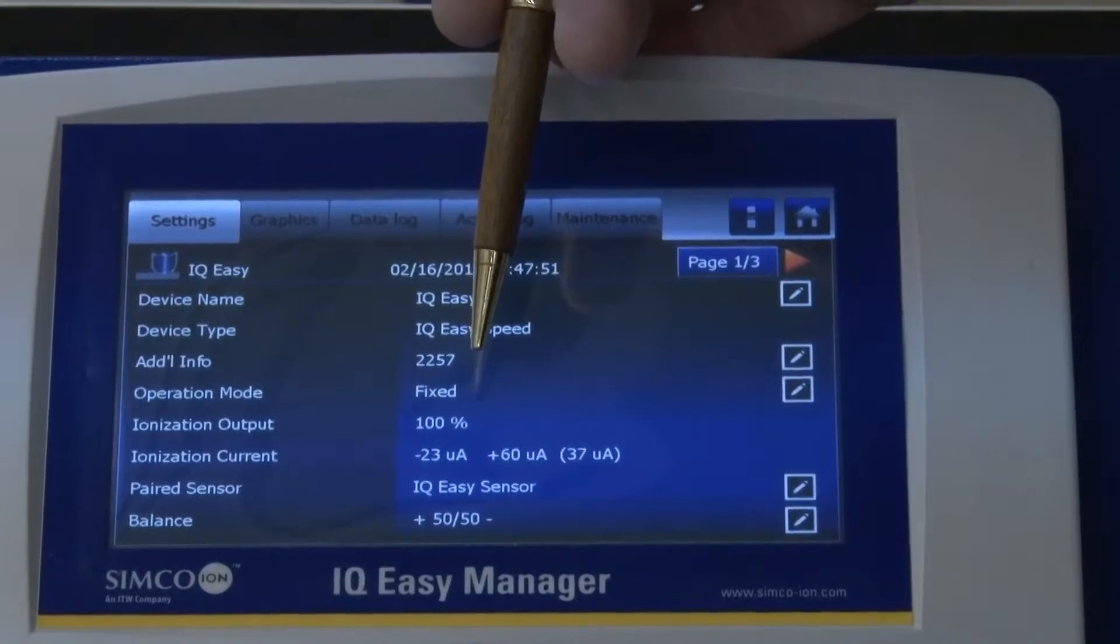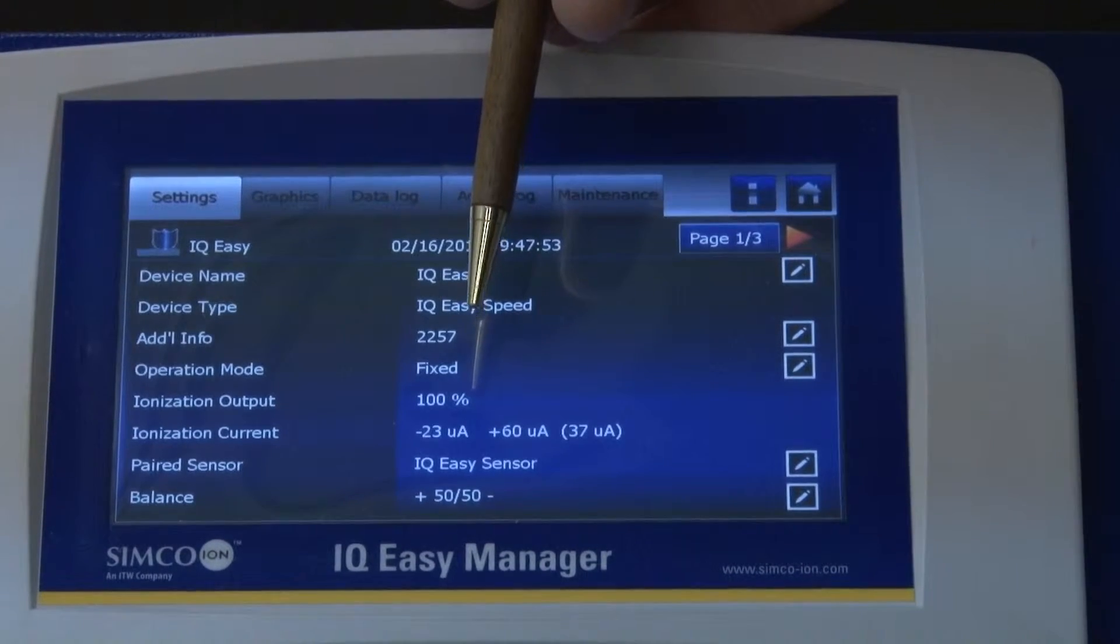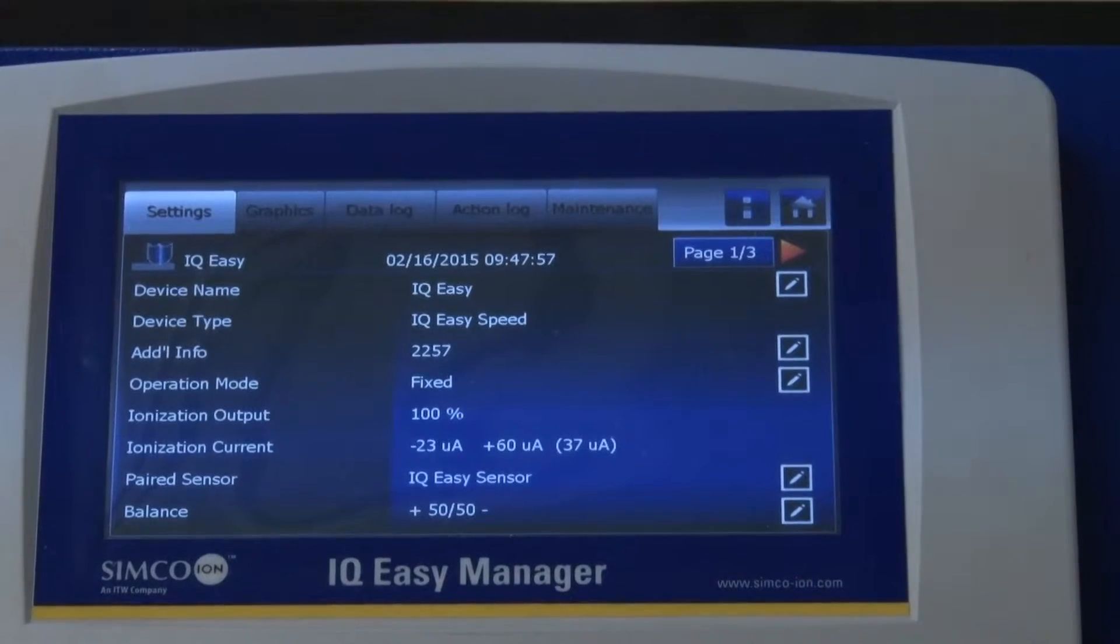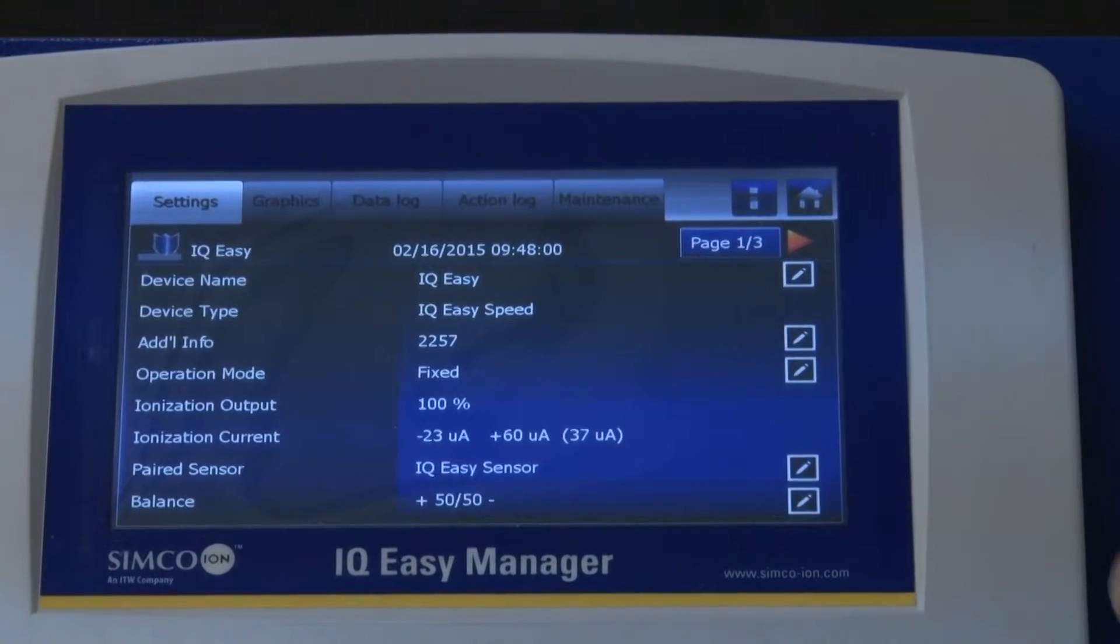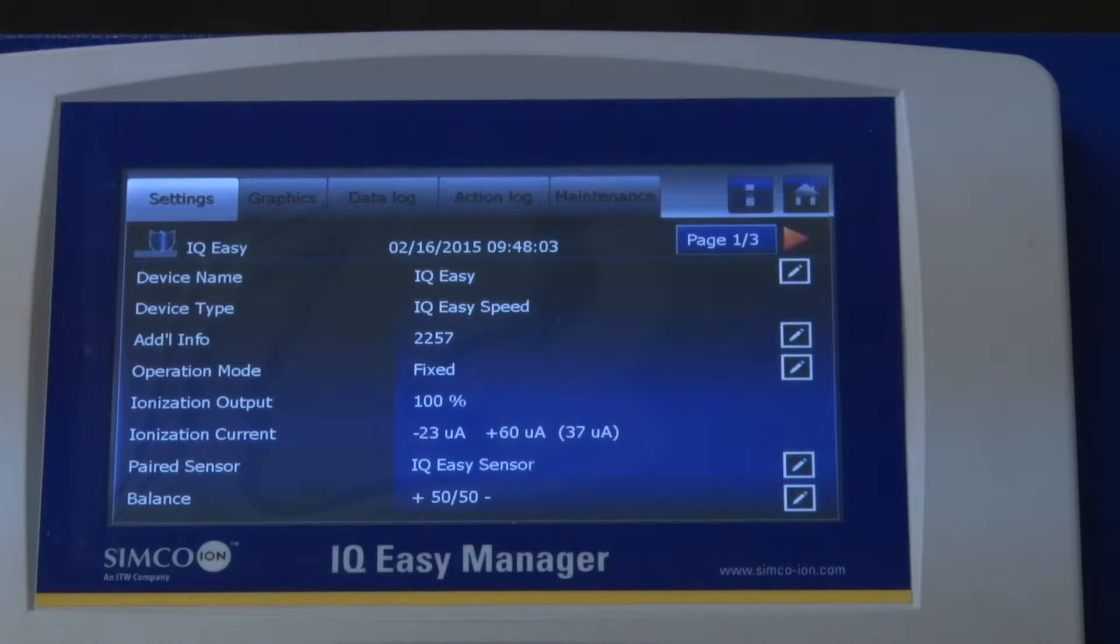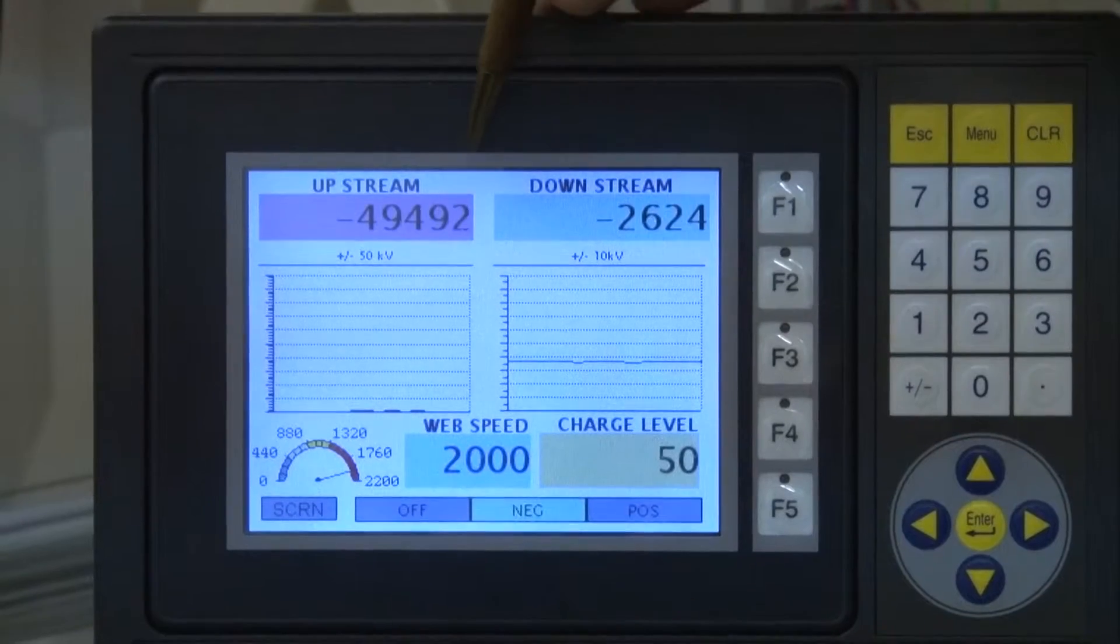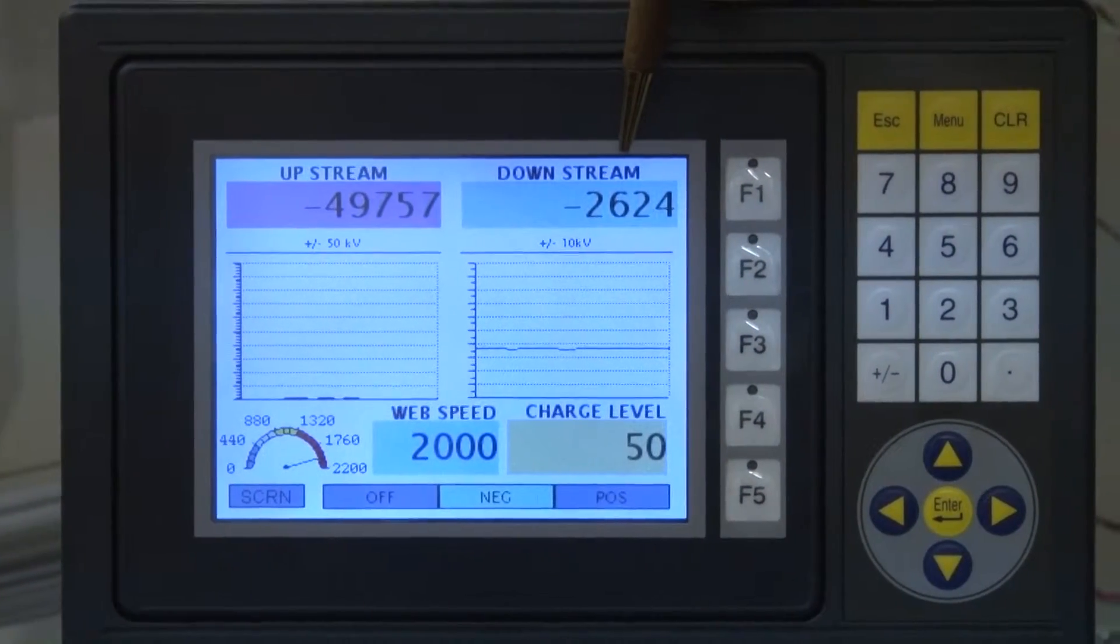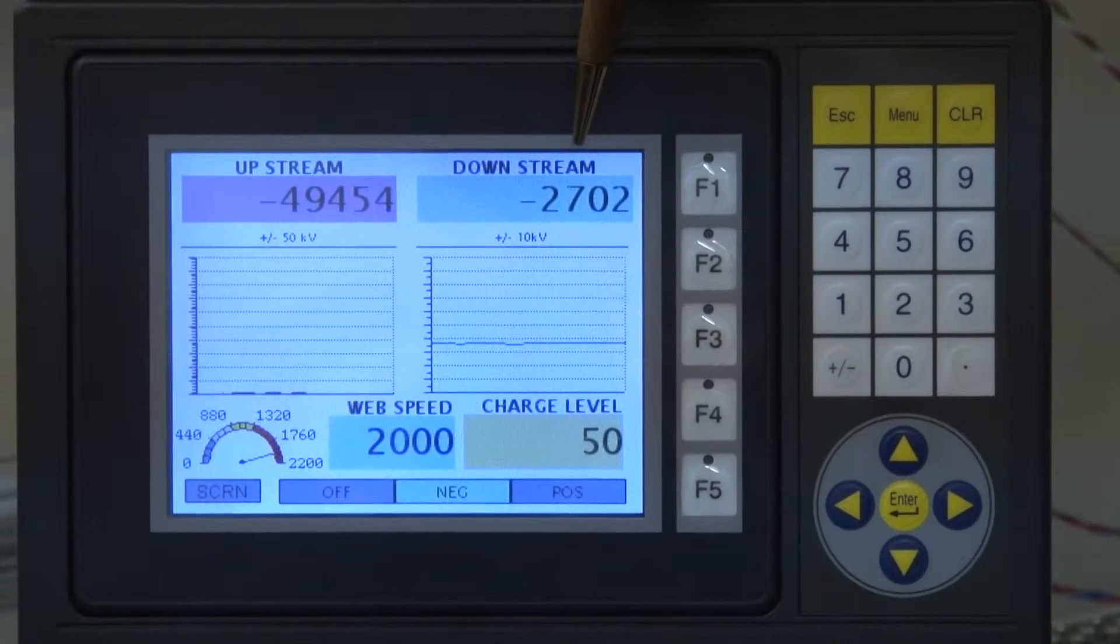Right now, the system has the neutralizing bar configured in the fixed mode. In the fixed mode, the positive and negative high voltage power supplies are run at roughly the same voltage, and the result is quite good in that mode. We're seeing that the net downstream charge from the neutralizing bar is about five percent of the upstream charge.